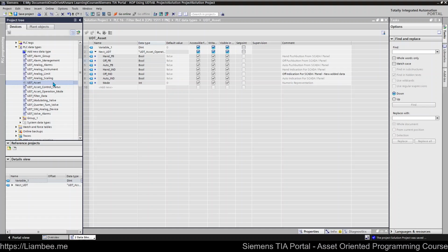And it's worth noting as well that once you've done this once and you've tested them and you've versioned them and you're happy that it gives you everything that you need, you've tested it with your function blocks, with your HMI, you're set then. And from a testing point of view, you no longer have to do basic functionality testing on every single type of asset. You're just doing integration testing then, making sure that the correct data set has been put to that asset.